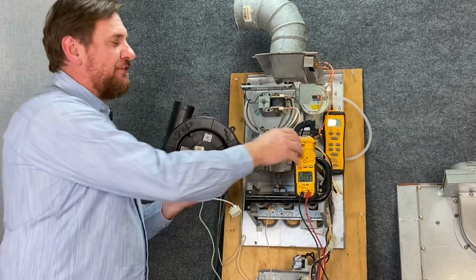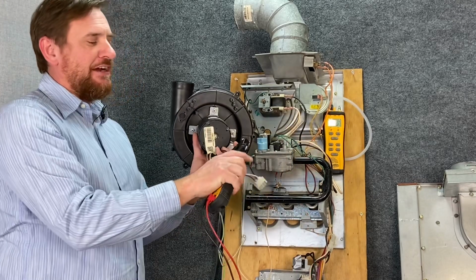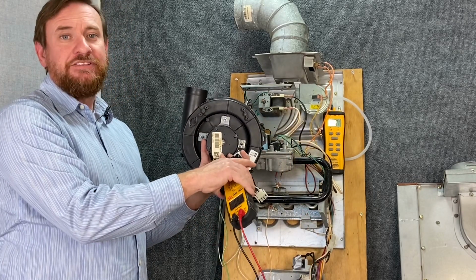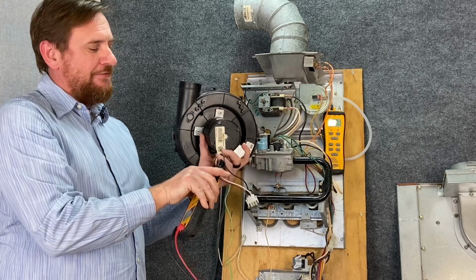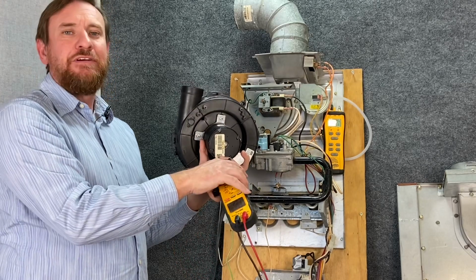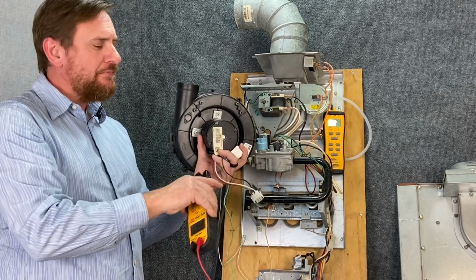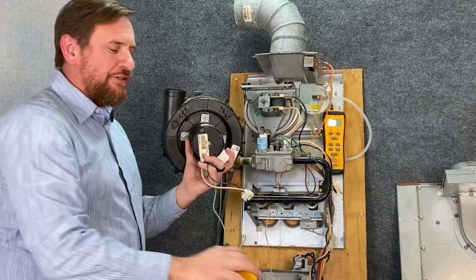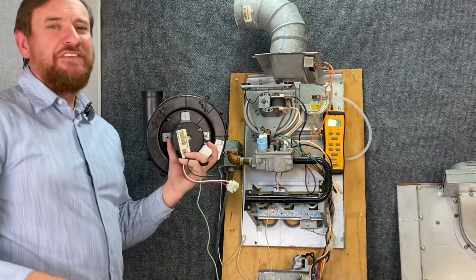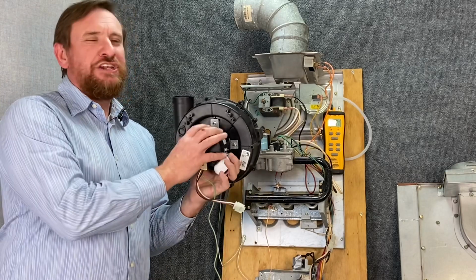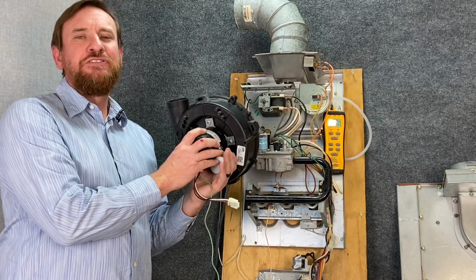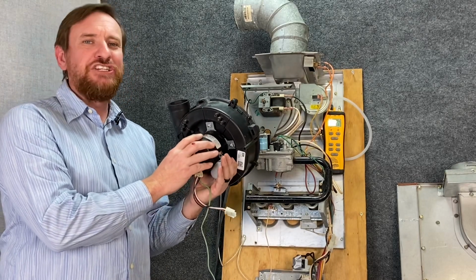So if you wanted to know if it's on high speed, you would clamp the meter around it. 0 amps means it's not using it. And if you check that on low speed and you get a number of amps, you know you're on low speed. It's a very simple way to check it. Some of the new gas furnaces are now even a step above that, where they have electronically commutated motors, which means they're full variable speed for a modulating system.